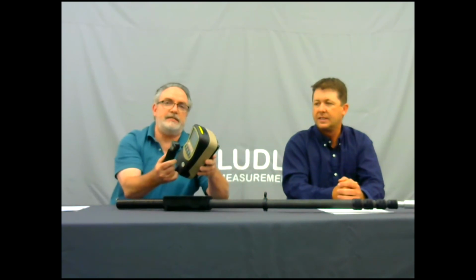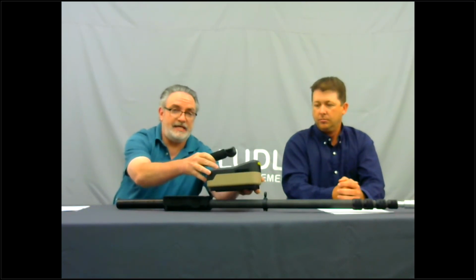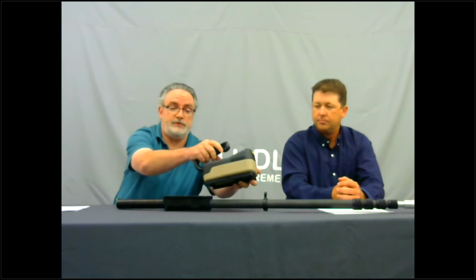The 3078 and 3078i are essentially the same unit in size and approximate weight. The difference being that the 3078i does have an internally mounted detector. It's located on the front of the instrument and can be used to measure integrated dose while you're doing your normal readings. As Ryan mentioned, it is easily detachable. It disconnects and can be removed from the instrument by pressing this little button, and then can also be used to survey as needed if you just want to use the internal detector for surveying, because the internal detector does have rate mode capability as well as scaler count, in addition to its integrated dose.